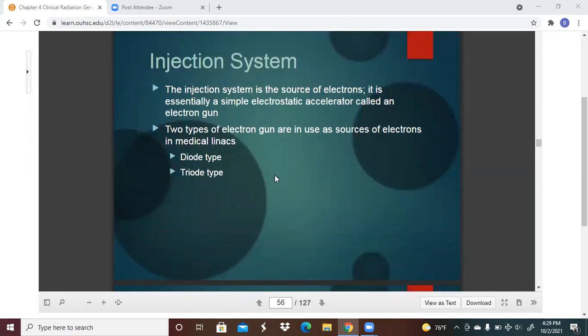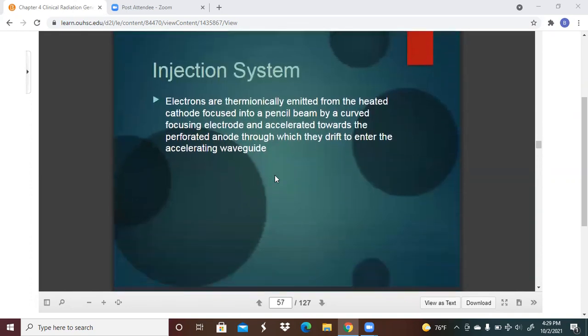So the injection system is the source of the electrons. It's usually a simple electrostatic accelerator called an electron gun. You've got 2 types of electron gun used as sources of electrons in medical Linacs: the diode type and the triode type. The electrons are thermionically emitted from the heated cathode, focused into a pencil beam by a curved focusing electrode, and accelerated towards the perforated anode, through which they drift and enter into the accelerating waveguide.